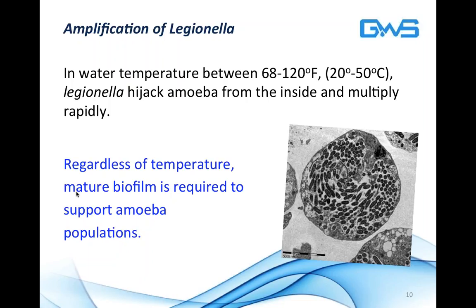In water temperatures between 68 and 120 degrees, Legionella hijack the amoeba and reproduce rapidly, becoming more virile and infective. Regardless of temperature, a mature biofilm is required to support amoeba populations, which are the amplifying vector for Legionella bacteria.